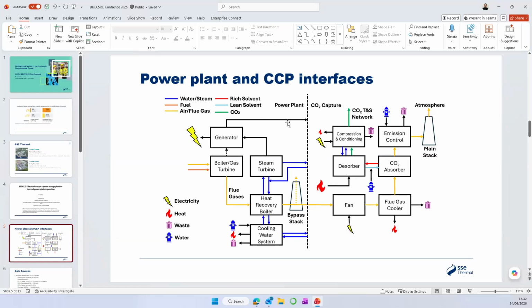You have a power demand to run the electricity requirements of the CCP. The two main requirements there are the compression and conditioning units and the flue gas fan, if included. Both of those are tens of megawatts in order of magnitude; for a 700 megawatt CCGT it is about 30 megawatts or something to that effect. Then you have smaller loads in the megawatt scale for pumps and heat tracing and the like. You have a substantially increased cooling water demand on your system, something of the order of a 40% increase, primarily for cooling down your flue gas from whatever the outlet temperature is, somewhere between 120 and 80 degrees, down to 40 degrees ish, and for basic heat rejection in the system from compressors and the like.